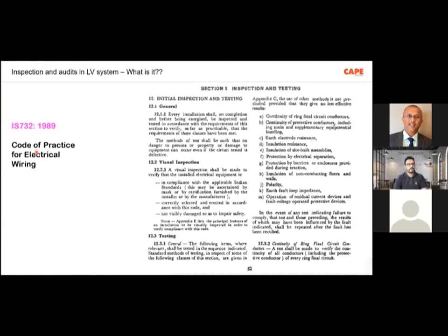And the next regulation says, all the products used in that particular installation shall satisfy the respective IS standard or the IEC standard. So basically, code of practice is for an electrical installation, and the standard is for a product. Now, IS 732, 1989, Code of Practice of Electrical Wiring, you can see the section 5, inspection and testing.